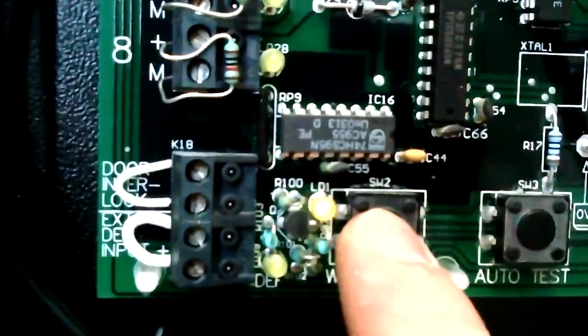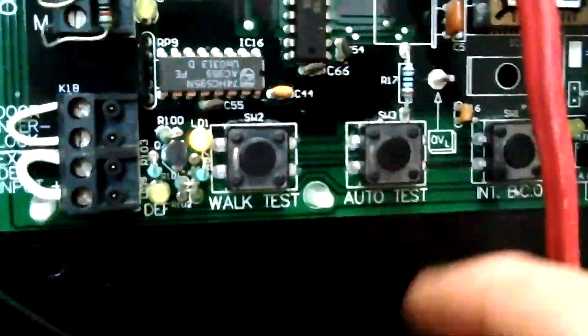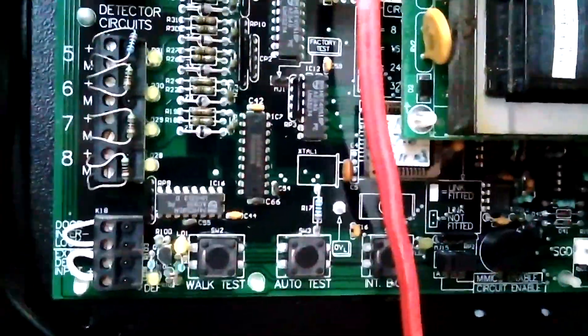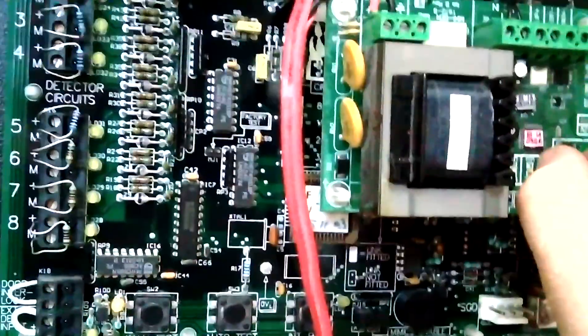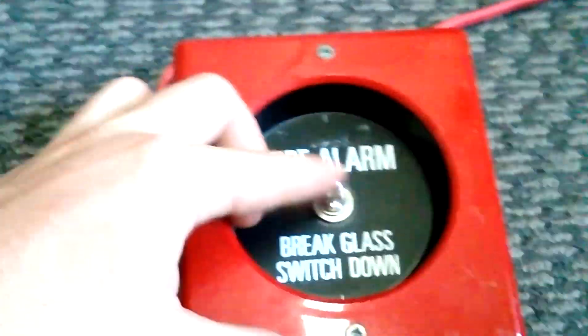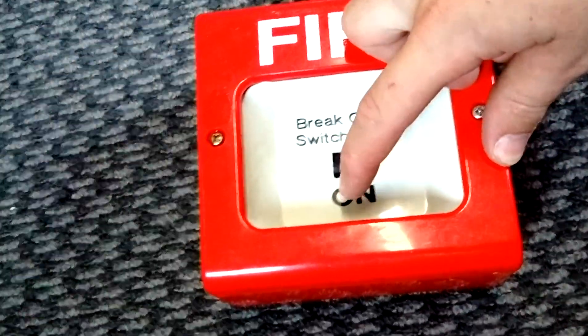Okay, one last cool function I will show you is walk test. So what you do is you've got this button here and you just hold it down and then it goes into walk test mode, take it off isolate and put it back on. That's good. We'll test. So we will set off this call point then it resets, try this one.